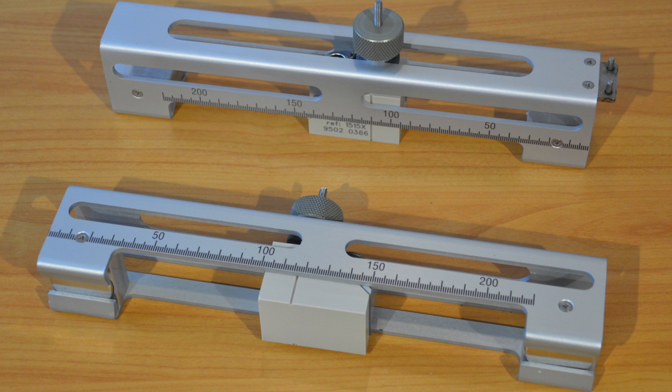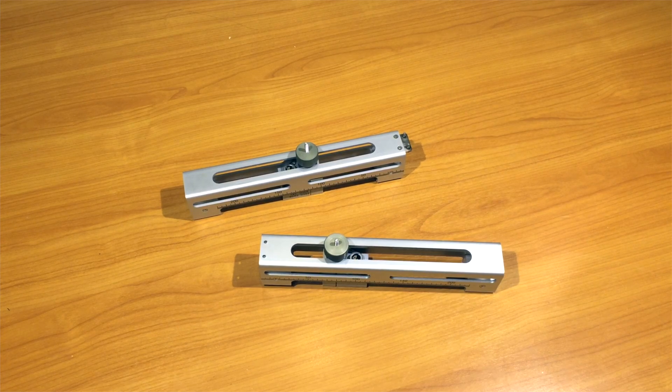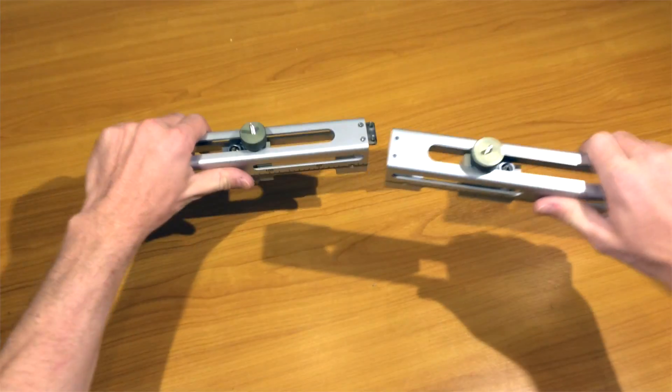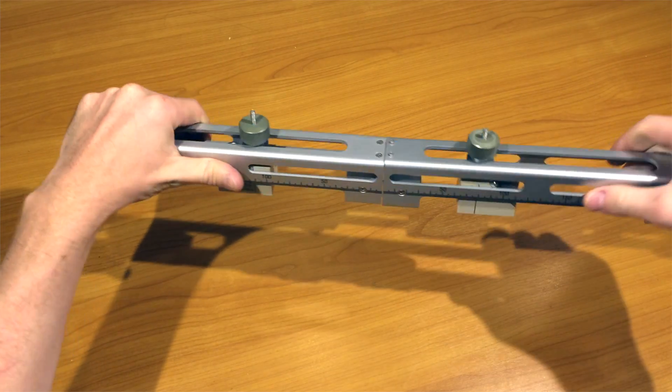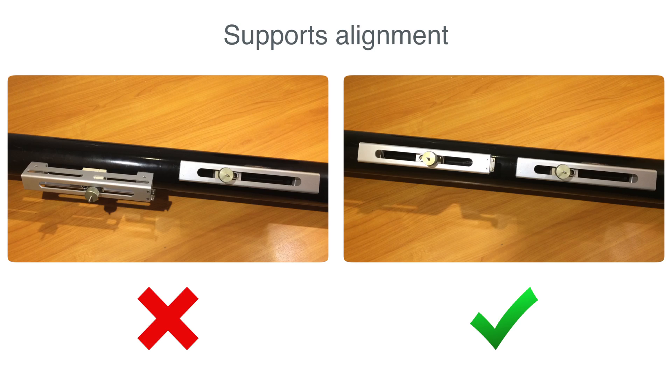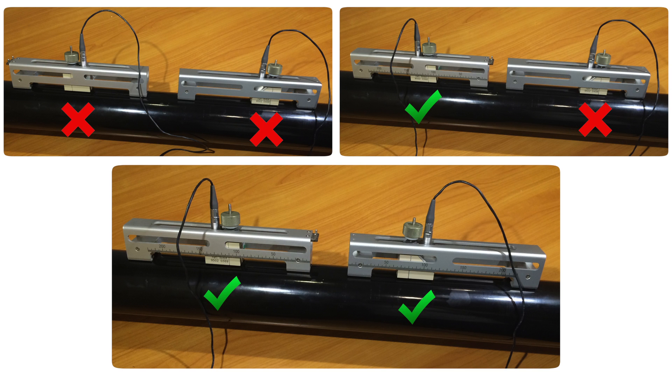The 1515 and 1599 probes have individual supports. If the probe distance is less than 350 mm, you should assemble them together. If not, align them properly and make sure the connectors for the cables are on the outside.